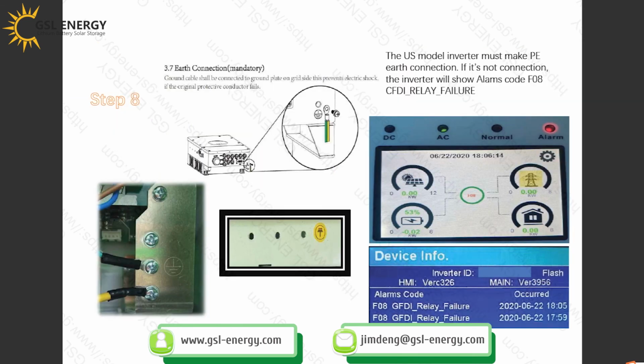The earth connection - you can check the manual for how to install the earth connection. In my install experience, the US model inverter must make the PE earth connection. If it's not connected, the inverter will show alarm code F08, which means the PE is not connected properly. You can check the user manual in the last 2 pages to see the alarm codes.